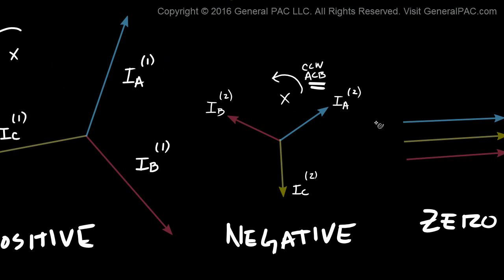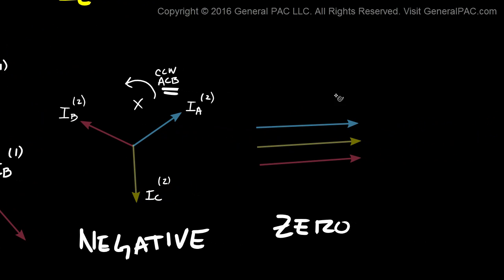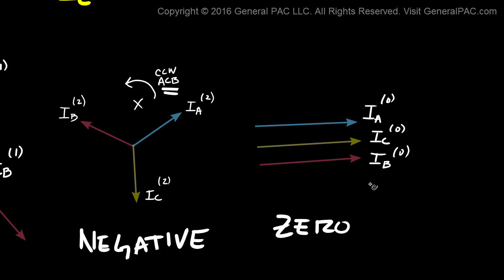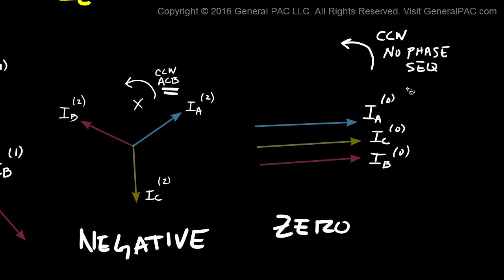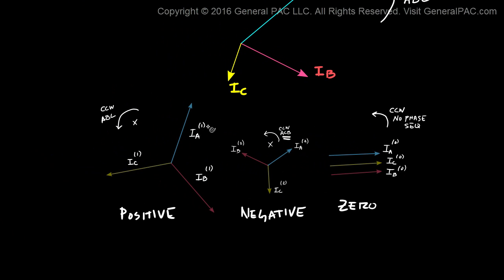Now we get to our Zero Sequence Component — let's zoom in here. This is IA superscript 0. This right here is IC superscript 0. And this phase here is IB superscript 0. The Zero Sequence Component is also rotating in the counterclockwise direction, but in terms of phase sequence or phase rotation, it has no phase sequence — meaning it's neither A, B, C nor A, C, B. In reality, these Zero Sequence Components actually overlap each other, but to make them easier to see, we've displaced them slightly.